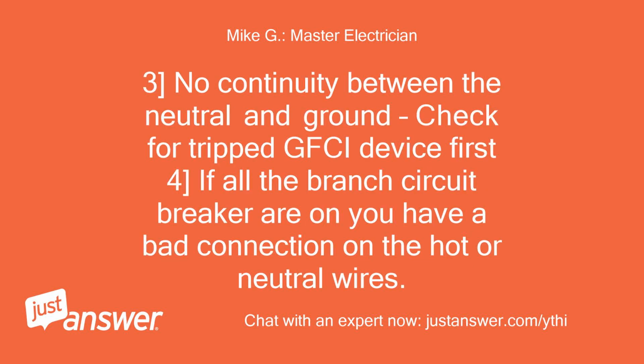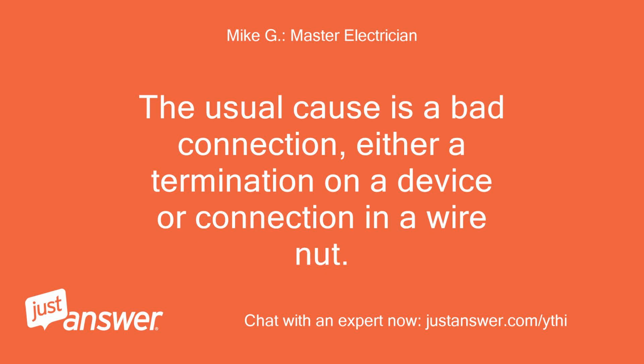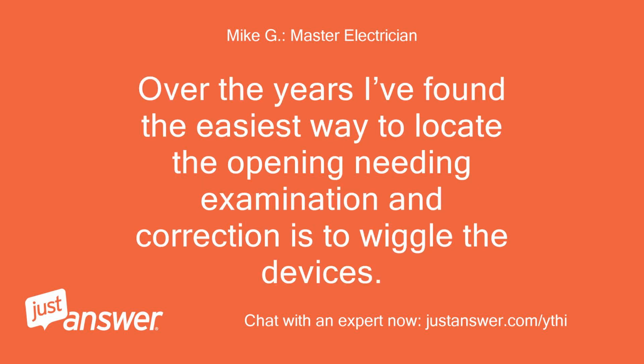3. No continuity between the neutral and ground. Check for a tripped GFCI device first. 4. If all the branch circuit breakers are on, you have a bad connection on the hot or neutral wires. The usual cause is a bad connection, either a termination on a device or a connection in a wire nut. Over the years I've found the easiest way to locate the opening needing examination and correction is to wiggle the devices.